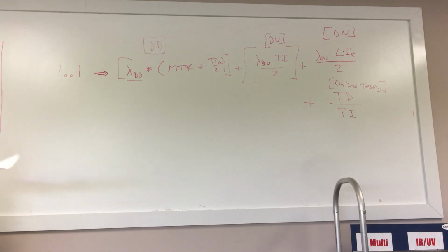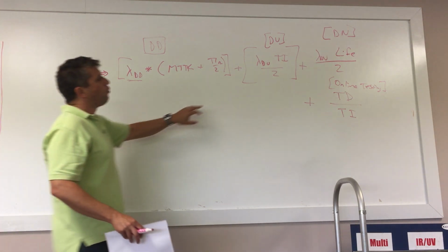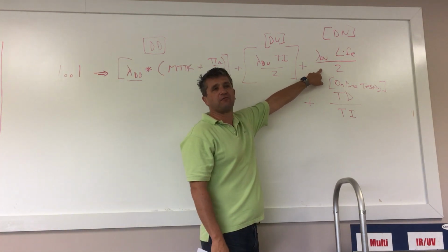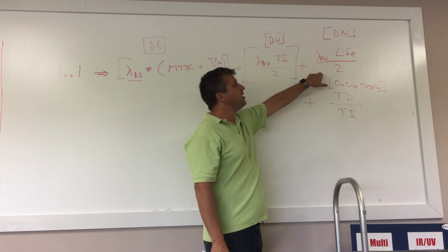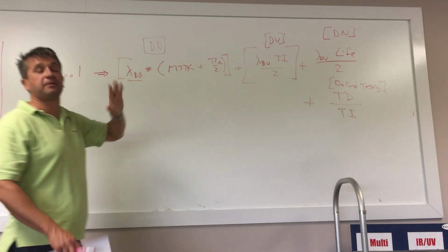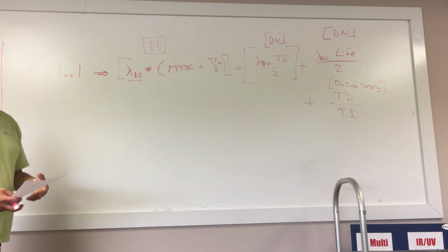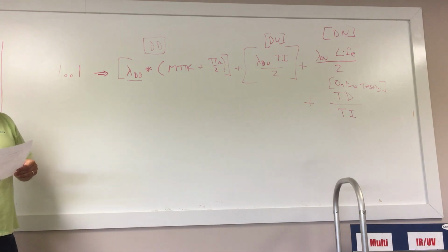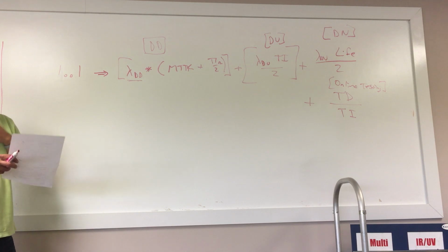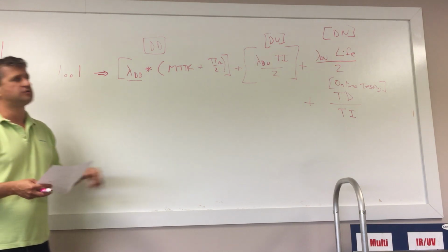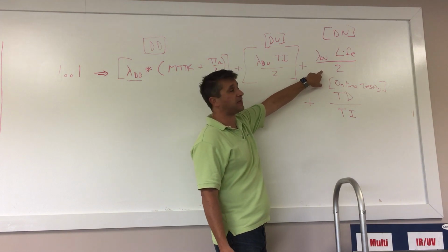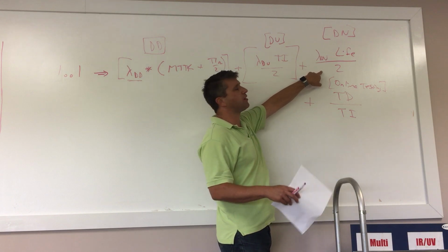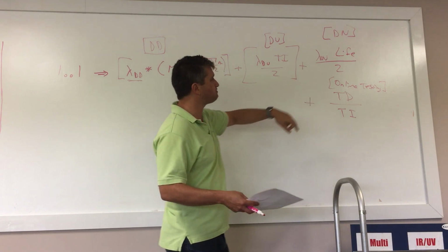historically was kind of ignored because the guidance from the industry professionals and practitioners was, we want to make sure that our proof tests are as close to 100% effective as possible. Therefore, we're going to ignore never detected because we assume 100% of the failures are detected. It's not that bad of an assumption, but I think we've gotten to the point where we really just can't ignore it. So most of the time, you're really going to want to see this lambda DN term. Okay, so that assumption that you have 100% coverage is generally not true.